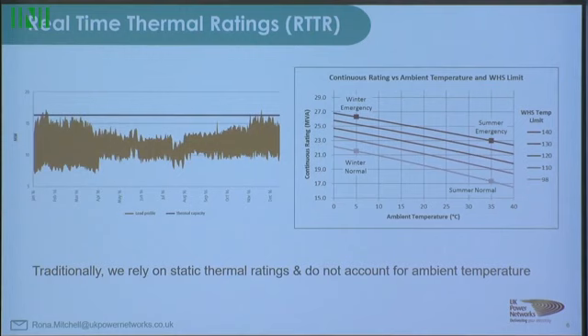Traditionally we only rely on static thermal ratings and don't take ambient temperature into account. We might have a summer rating and a winter rating, sometimes an emergency rating. But the rating actually varies with the ambient temperature of the transformer. Traditionally we have one rating for summer, assuming ambient temperature at 35 degrees Celsius - but summer isn't 35 degrees every day, I wish it was, but it's not. Again for winter we assume it's 5 degrees all the time, but on cooler days we can actually run the transformer harder and put more flow through it, maximizing the utilization of our assets.